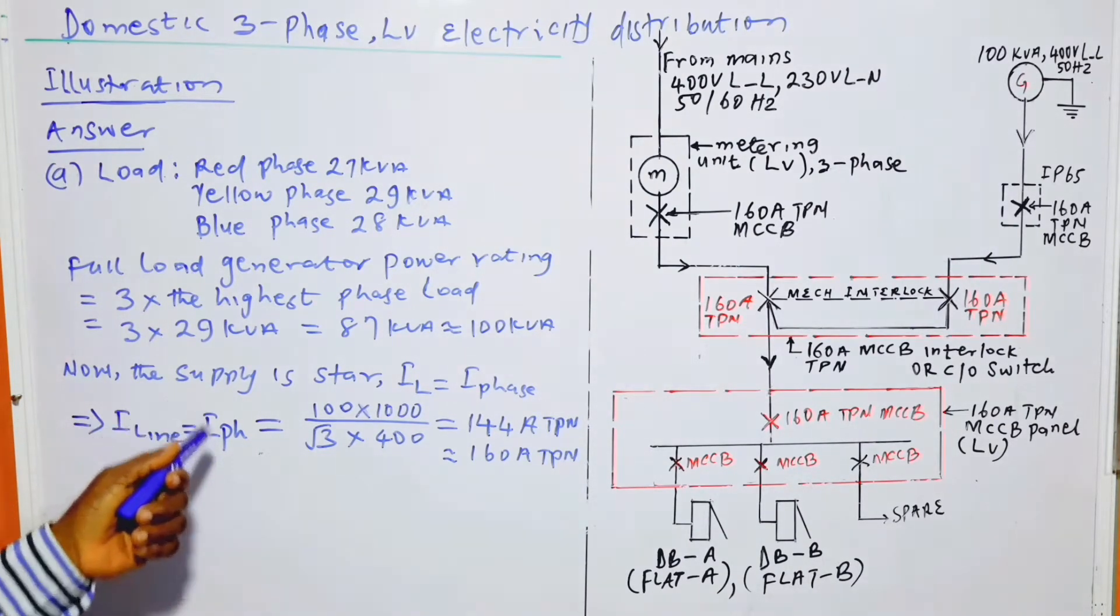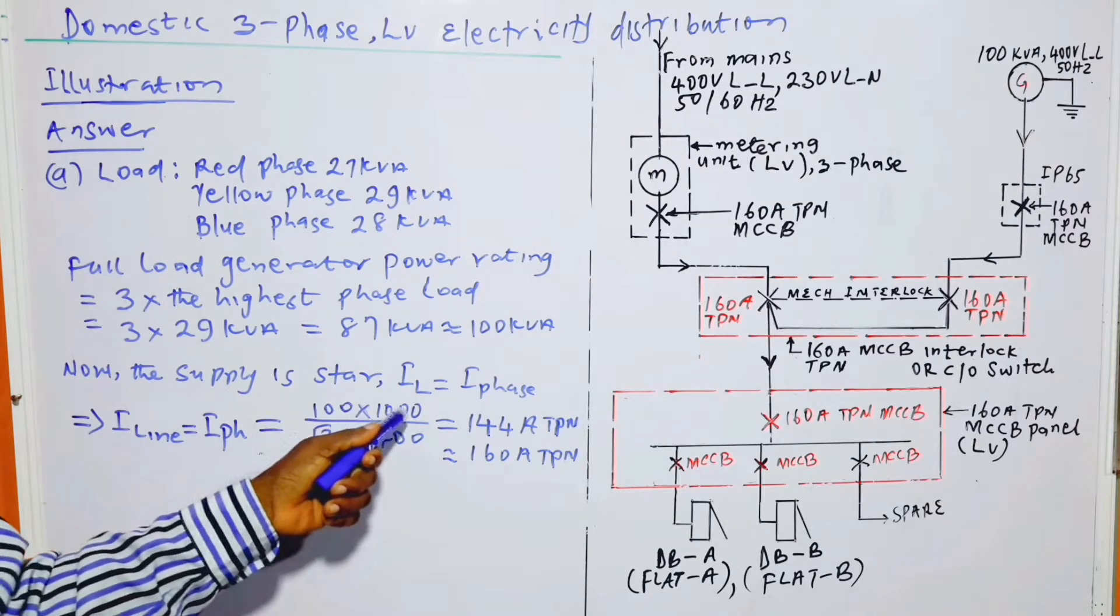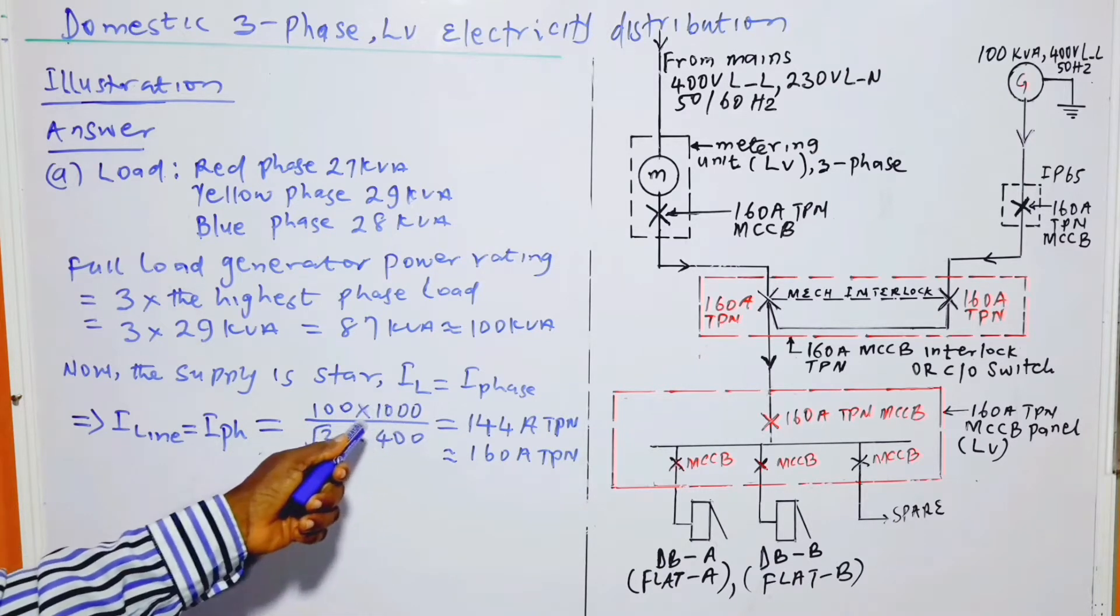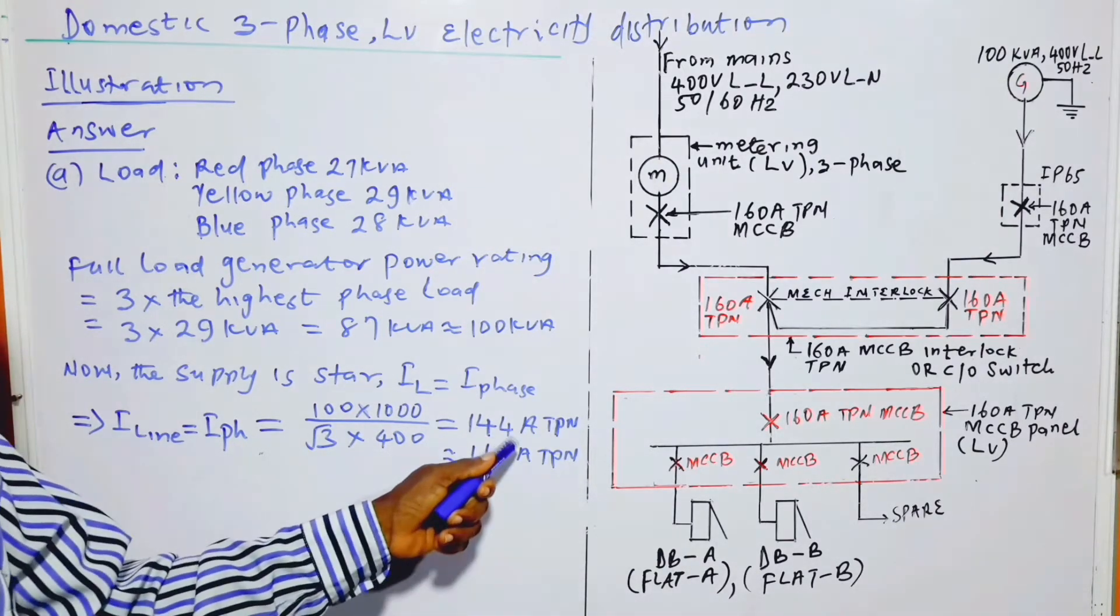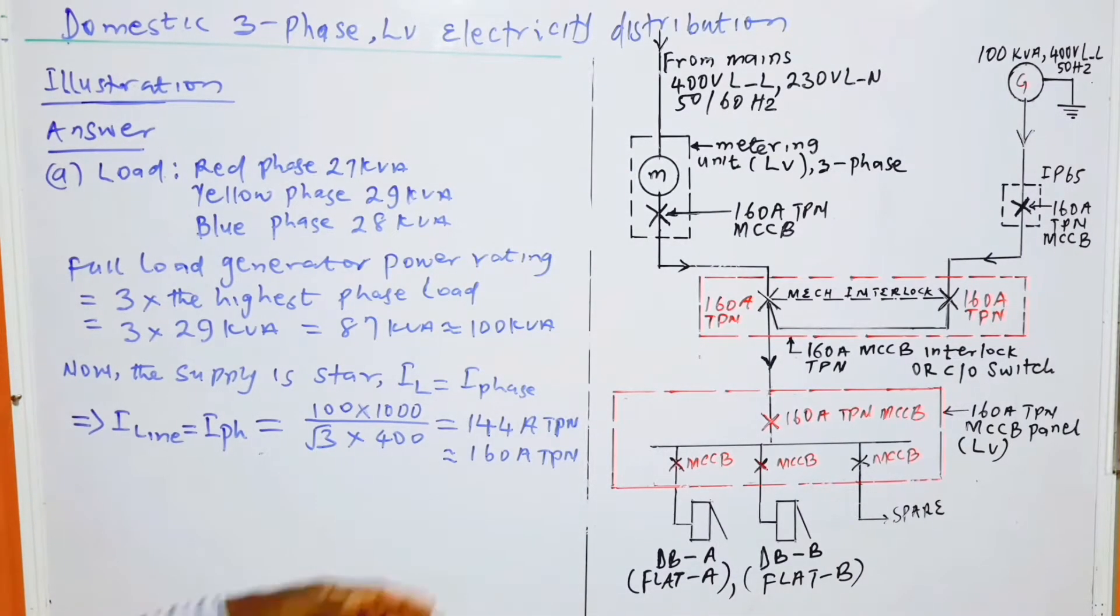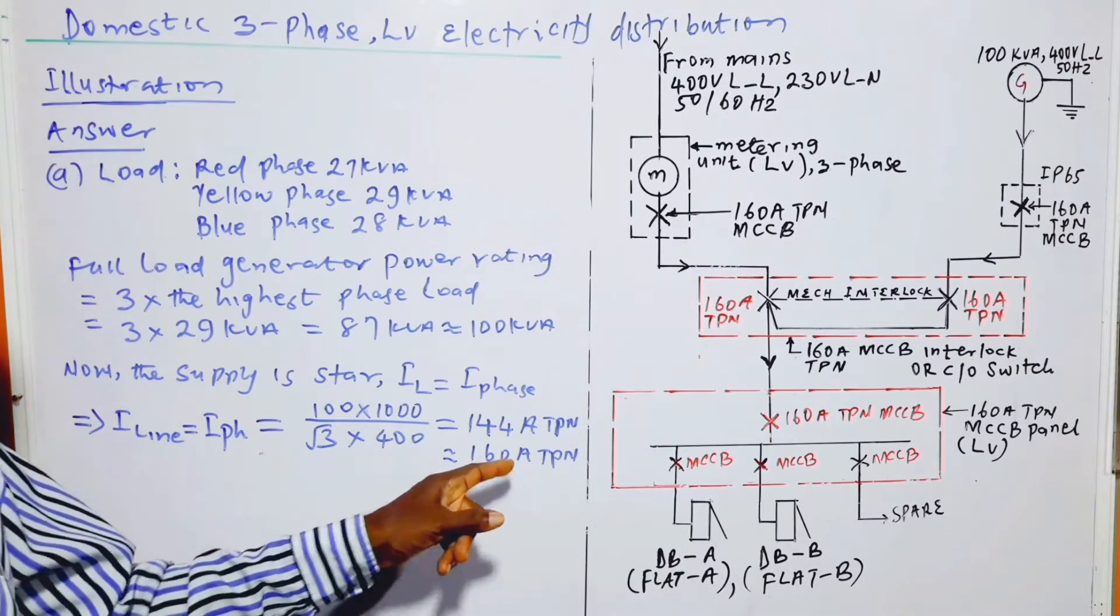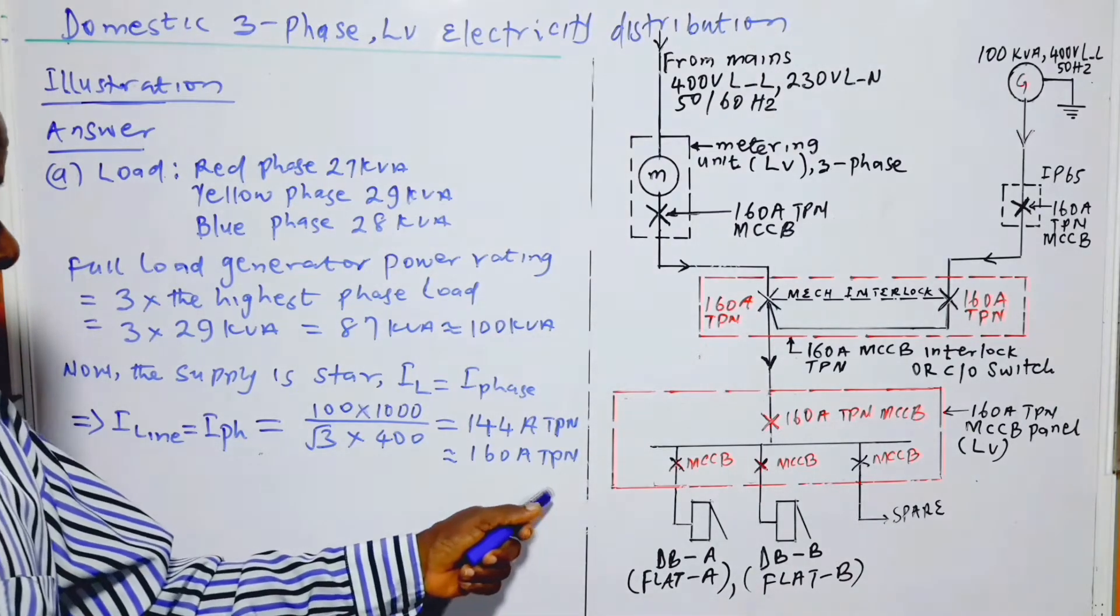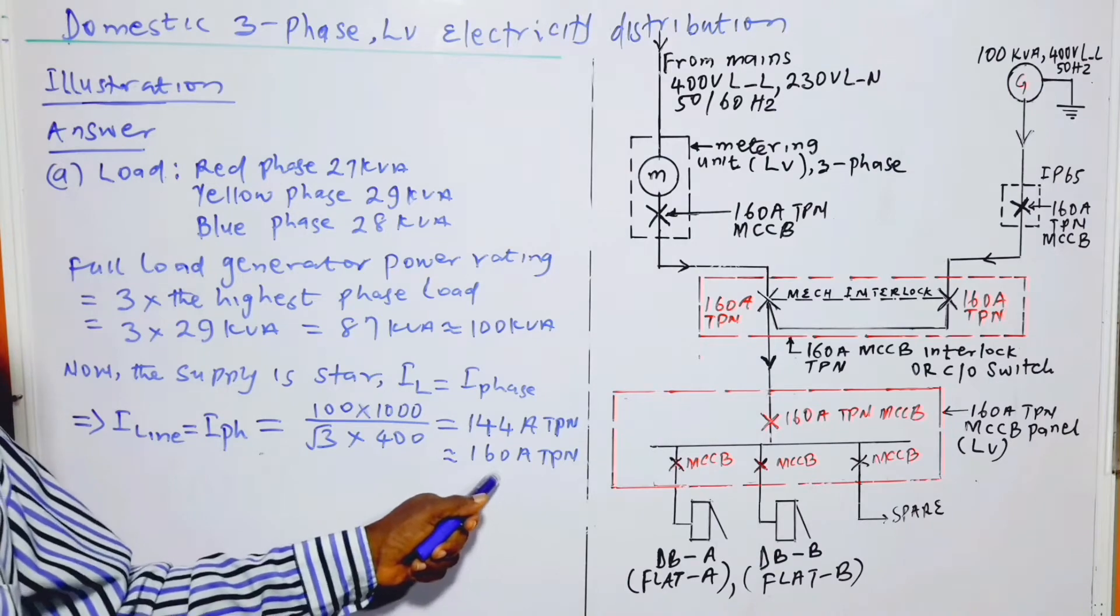When we have star connection, I-line equals I-phase, and the value is calculated as 100 times 1000 divided by root 3 times 400, and that is 144 amperes. The next available circuit breaker in the market is 160 ampere triple phase with neutral. This is MCCB.